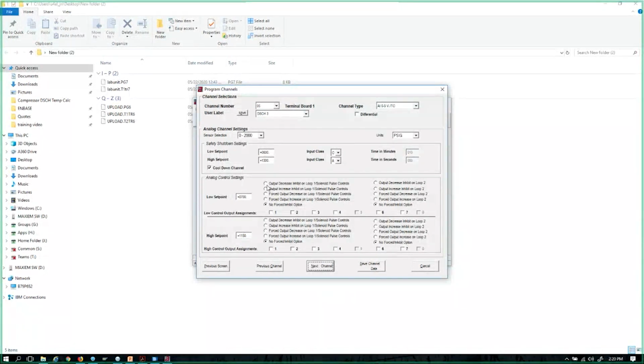But let's take a look at this. Output decrease inhibit on loop 1. Output increase inhibit on loop 1. So what we're saying with inhibit is we can't increase it, we can't decrease it. Force output decrease on loop 1. Force output increase on loop 1. With these two force options, we can force it to decrease or force it to increase based on a condition. So I selected channel 5, third stage discharge pressure, for a reason here.